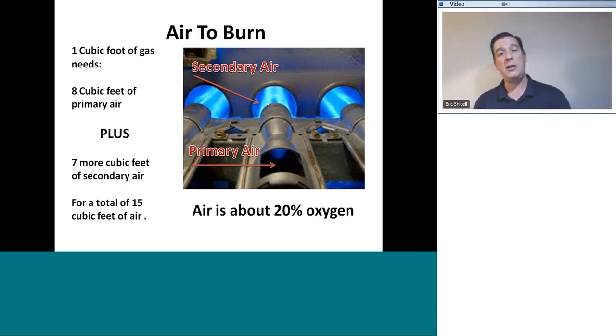So additional air is allowed into the flame to give even more oxygen. So there is an overabundance of oxygen so that hopefully all of the fuel gas molecules will find an oxygen partner to bond with. And that's the idea. If it weren't for that extra 7 cubic feet, it'd be kind of like a game of musical chairs, right? When there's a bunch of nitrogen sitting in some of the chairs and it's in the way and the oxygen doesn't have a chance to join the party and sit down. So that's why we give even more air to get an overabundance of oxygen. So if we could get rid of all that nitrogen out of the system, that wouldn't be necessary. But we're working with air, so it is necessary.